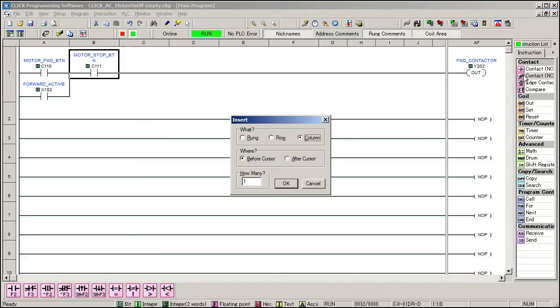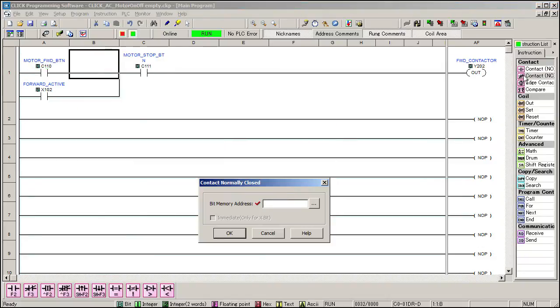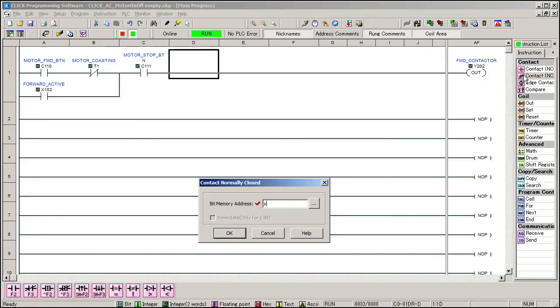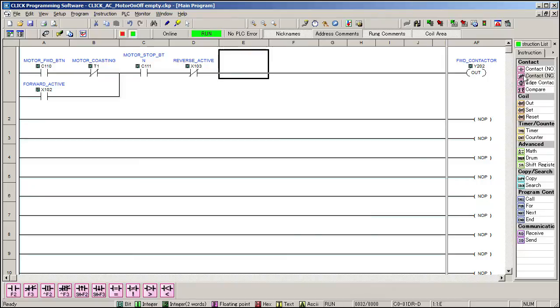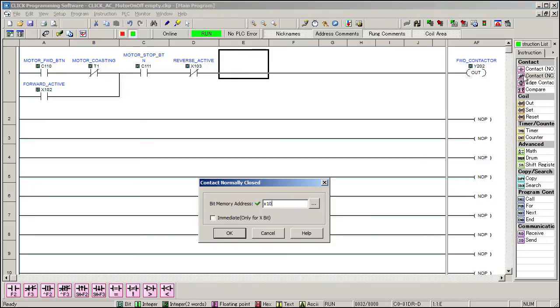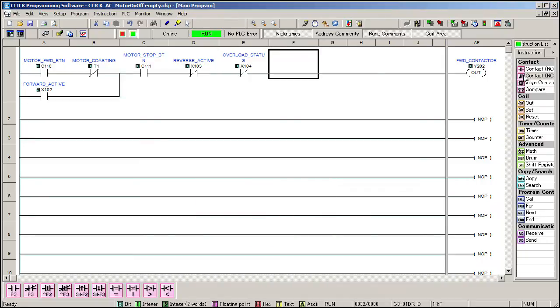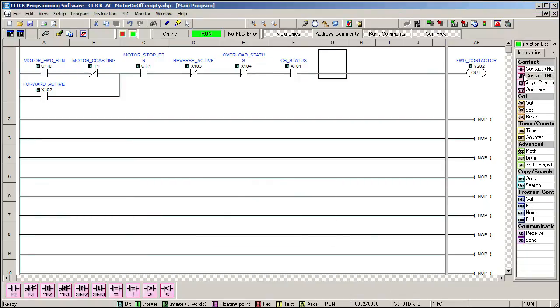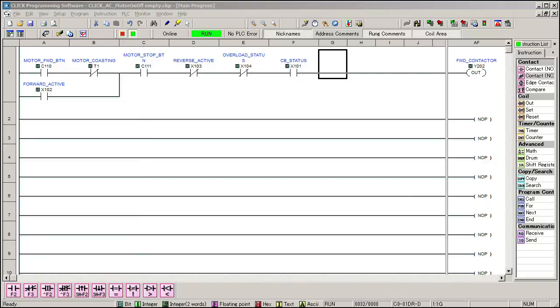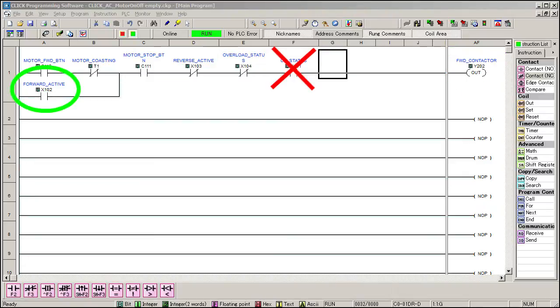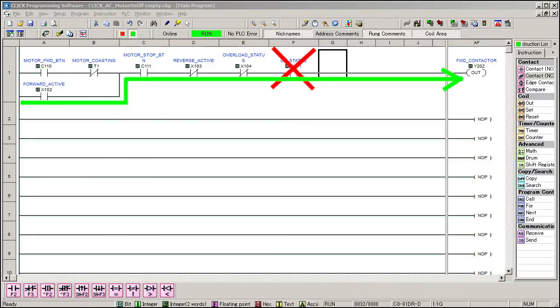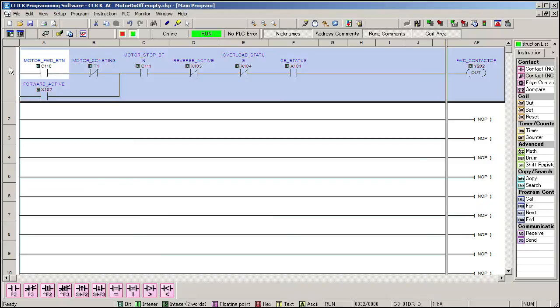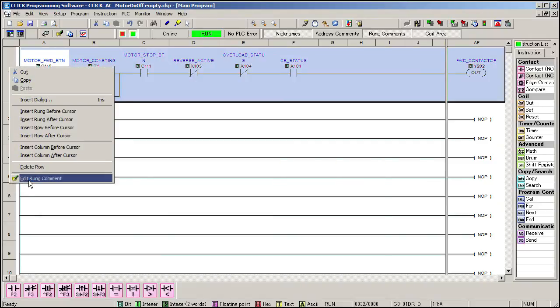We only want the motor to be started if the motor is not coasting. We'll create that in just a minute. And we want to make sure that the reverse contactor is not engaged. We don't want to run the motor if the overload is tripped. And finally, we don't want the motor to be enabled if there is no power. This serves as a handy reminder to check the power of course, but more importantly it makes sure the motor can't be latched or sealed in while the power is off. If we didn't check the circuit breaker status, then there is nothing to prevent this ladder code from energizing the contactor which enables the AUX contact and latches or seals in the circuit. So when the power is applied, the motor will already be enabled and it will jump to life. Normally, we don't want that to happen so adding this contact to prevent the circuit from latching while the power is off is a really important safety feature.